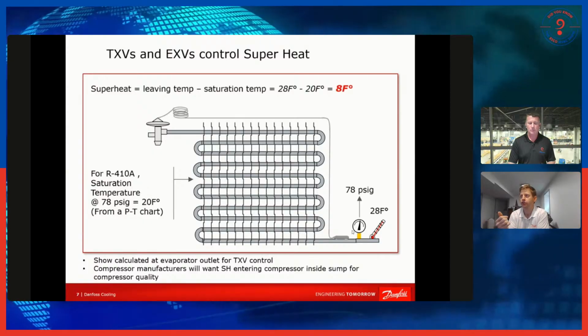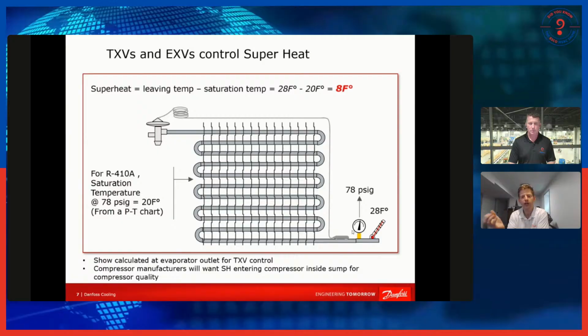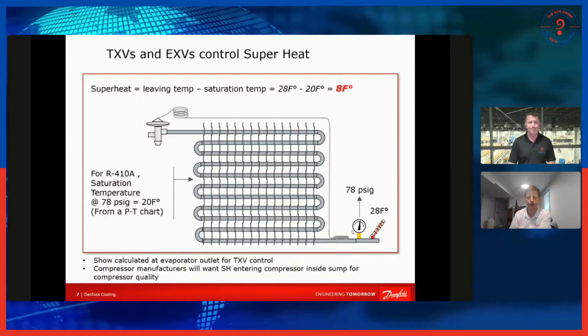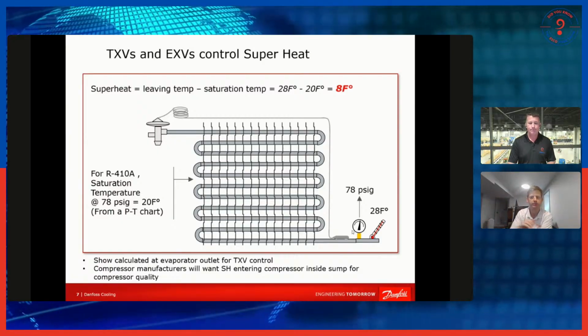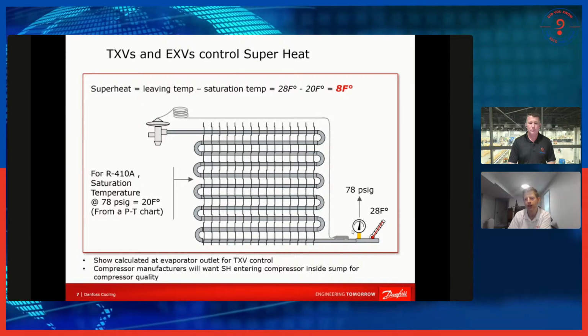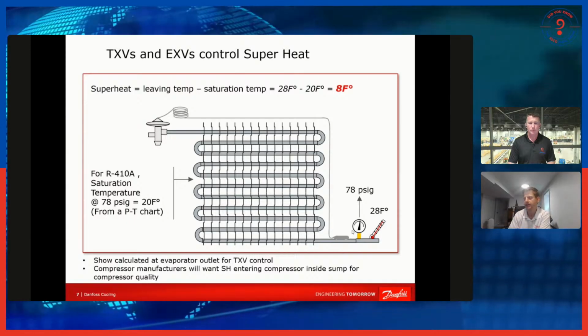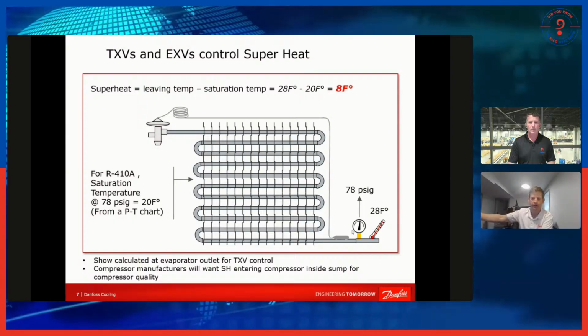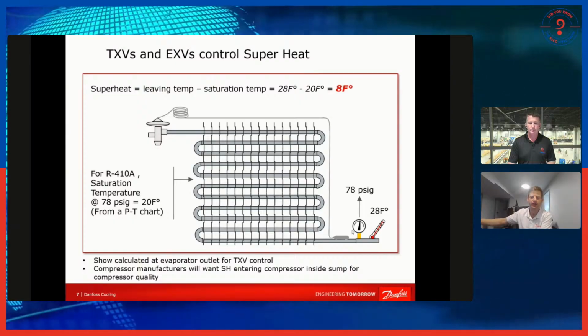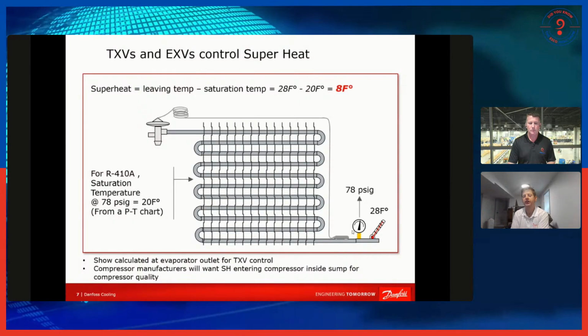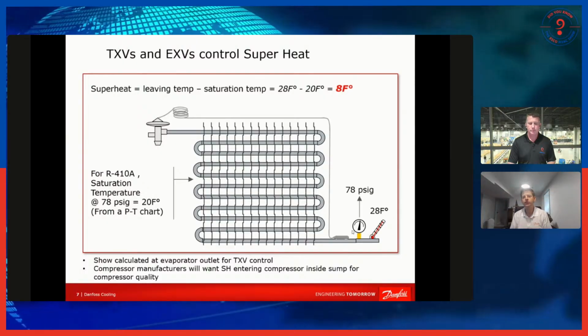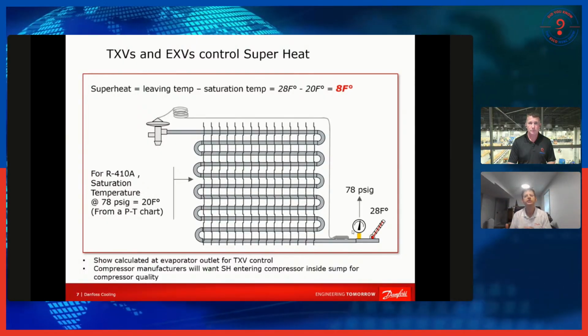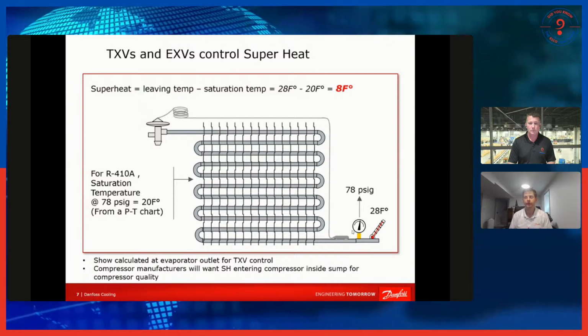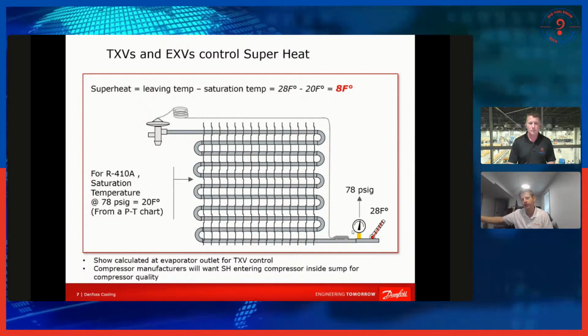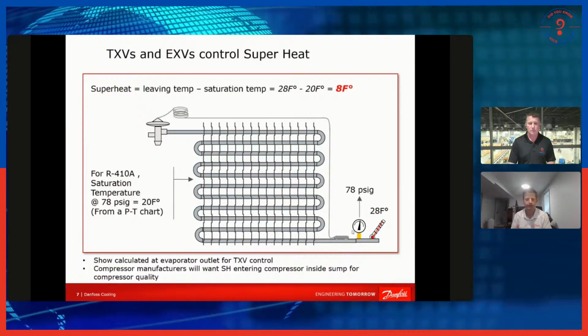So if you're looking to troubleshoot, a good thing to consider is, well, where do they have the bulb? Where do they have the external equalizer? Where is my temperature sensor? Where is my pressure transducer? And that might help give you at least an idea. If you're measuring superheat entering the compressor, you expect it to be higher than what it is at the evaporator coil itself. And then depending on how long your runs are, is there a 4-way valve there? Those things might give you clues as far as, well, yeah, it should be much higher at the compressor than it is at the evaporator, and vice versa.